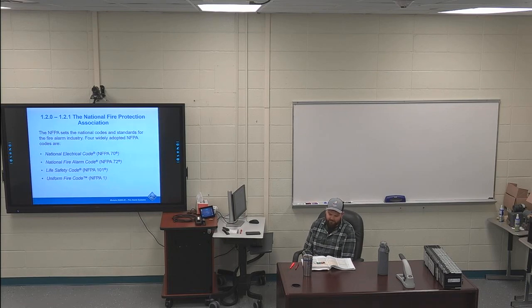Next bullet point is highlighted, the Uniform Code. You need to know that is NFPA 1. This code was established to help fire authorities continually develop safeguards against fire hazards. I also have the last sentence of that bullet point highlighted on the right-hand side of page 3. Information and requirements for testing, operation, installation, and periodic preventative maintenance of fire alarm systems are included in this portion of the code. So those are the codes.